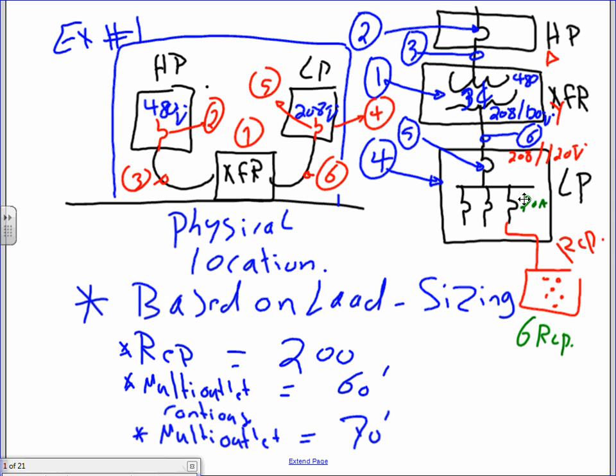You will be a fool if you feed your lights, if you burn your lights, at 120 when you have 277 volts. Why? Some of you will say, how about my lights? Well, why am I going to feed my lights from there? Your lights typically will be fed from where? The main panel, 277. Why is it important, if you have a higher voltage in your building, to burn your equipment at higher voltage? Efficiency. Your equipment is more efficient if you have higher voltage across it.